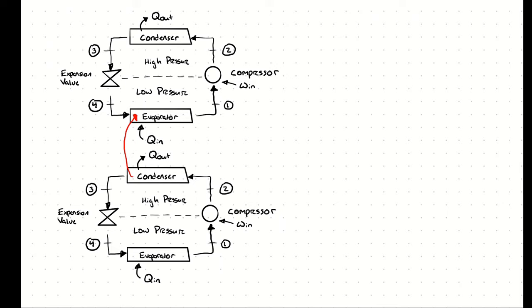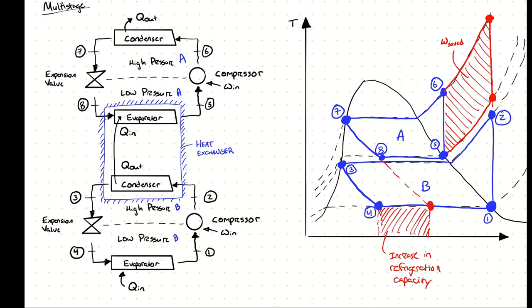We can improve the performance of a multi-stage refrigeration cycle by enclosing the condenser and evaporator together in a heat exchanger. As a result of this multi-stage refrigeration cycle, we can increase the refrigeration capacity corresponding to a certain temperature difference between high and low side saturation temperatures, and we have also decreased the amount of work required to operate the cycle. So we are decreasing the work in and increasing the refrigeration capacity, leading to a higher coefficient of performance.